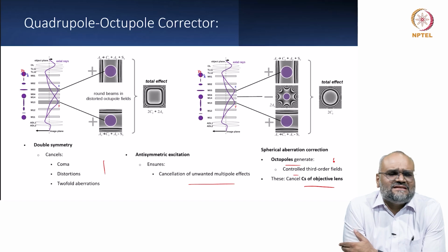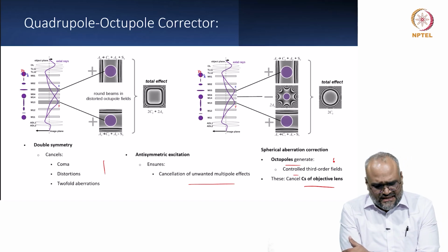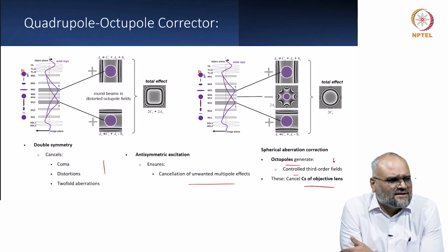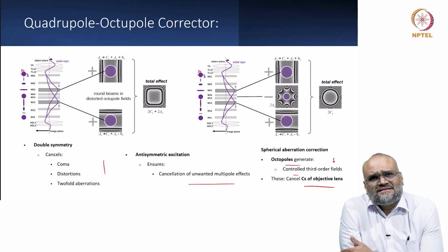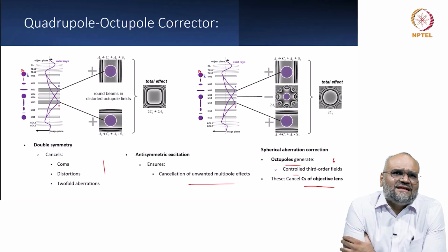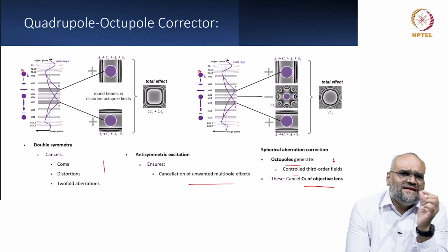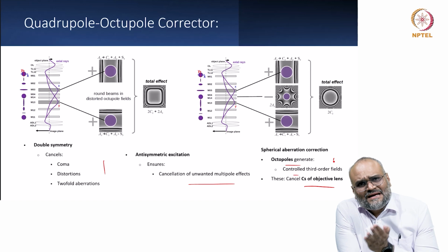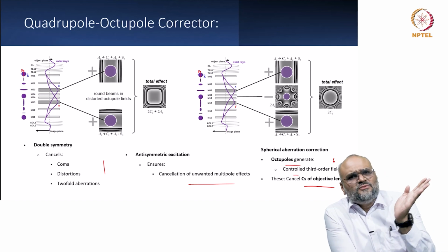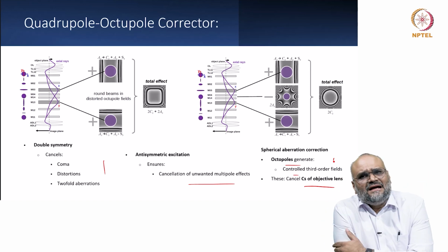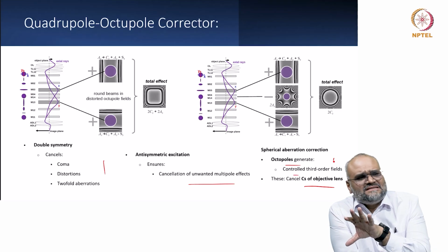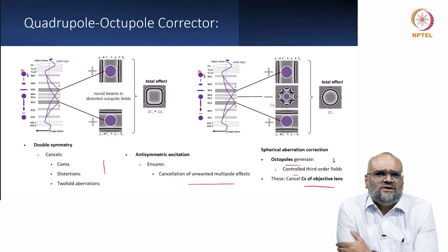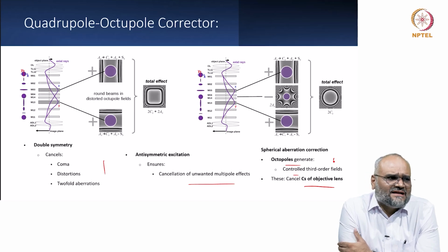corrector. So what happens is, if one of the quadrupoles I am replacing with the electric component, for any small distortion in the incoming electron wavefront, if there is any gradient in the energy, the faster moving electrons bend more inward and the slower moving electrons bend more outward, and you are now compensating for the chromatic spread, and with this kind of construction you can also have chromatic aberration correction as well.